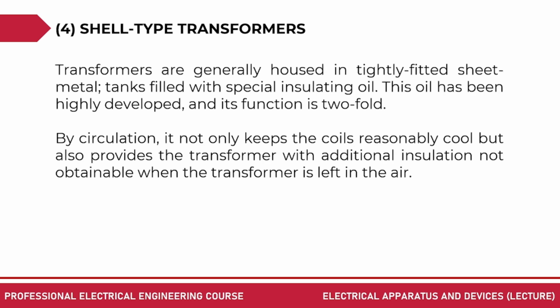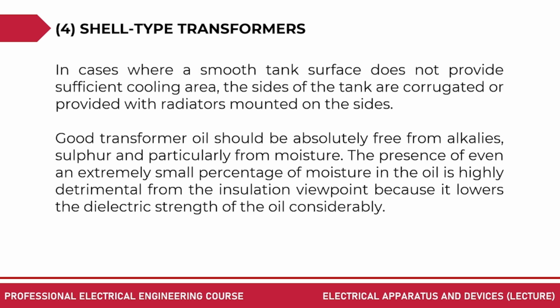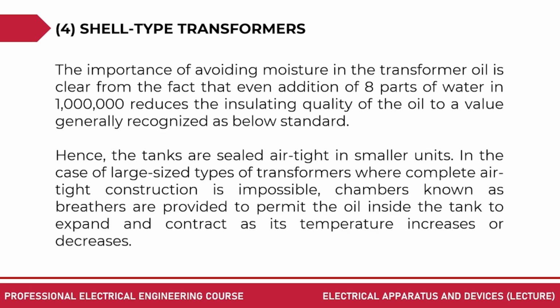Transformers are generally housed in tightly fitted sheet metal tanks filled with special insulating oil. Okay, next. The importance of avoiding moisture in the transformer oil is clear from the fact that even the addition of 8 parts of water in 1 million reduces the insulating quality of the oil to a value generally recognized as below standard. Hence, the tanks are sealed airtight in smaller units.